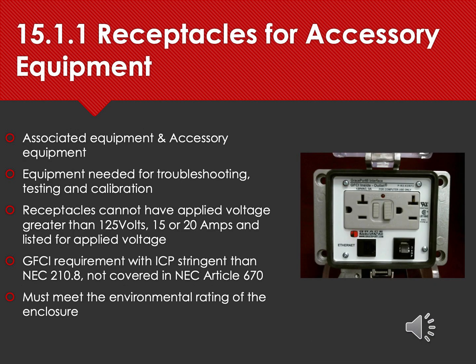This slide talks about the receptacles for accessory equipment as defined in NFPA 79, Chapter 15.1.1. In NFPA 79 context, we need to understand the differences between associated equipment and accessory equipment. Associated equipment is required for normal operation, while accessory equipment is not required for normal operation. That's a simple definition. Accessory equipment may be needed for maintenance, testing, calibration, or troubleshooting, and other maintenance-related activities. So basically, if you're performing a programming change, you may want to use an accessory receptacle outside your cabinet, as shown on this slide, okay?